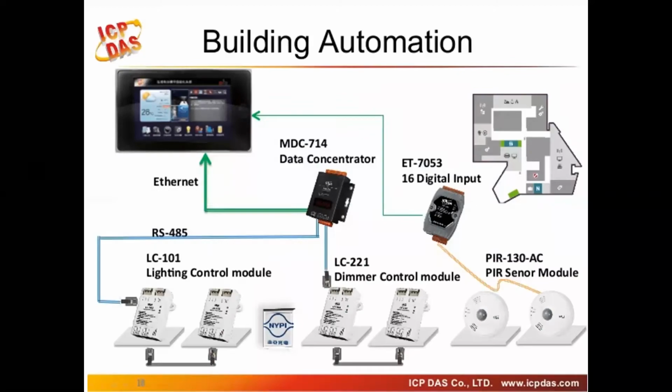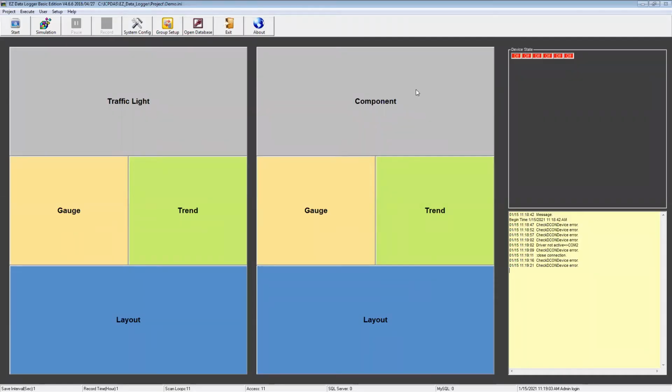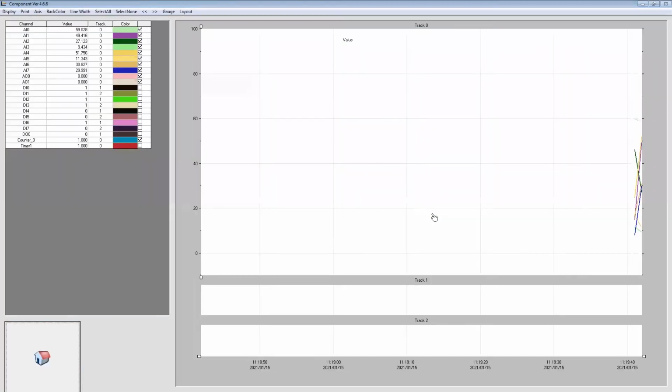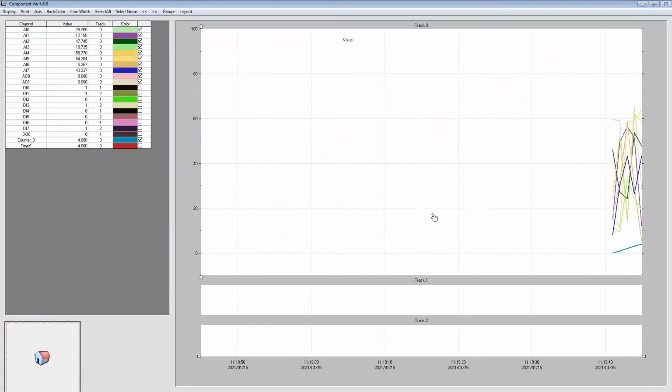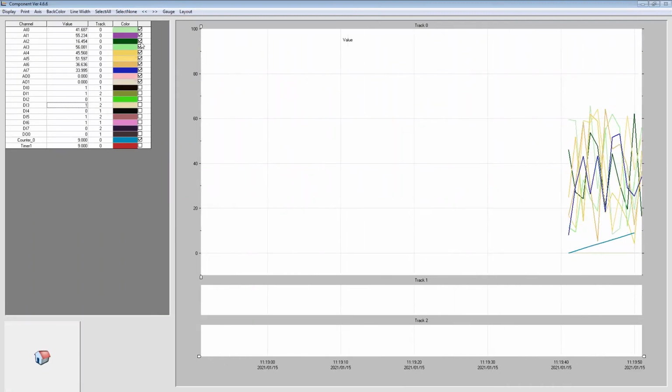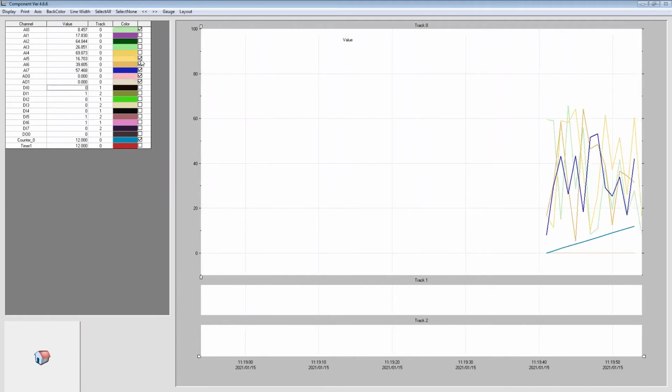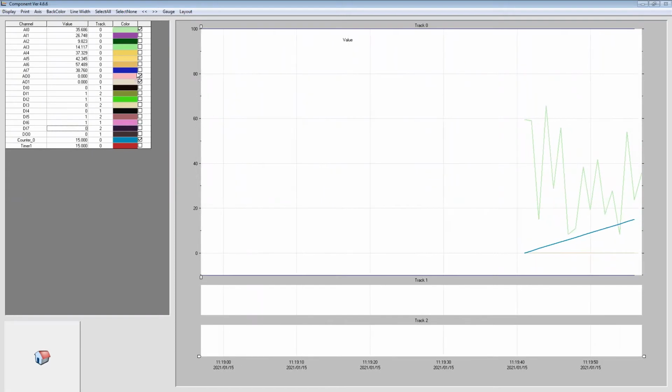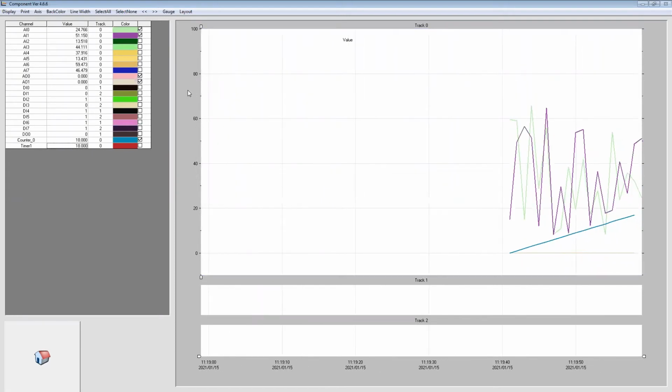Let me give you a snapshot of the software. Okay, this is our EZ Data Logger demo that comes with the software, just to show off the capabilities of the software. Let me enter simulation mode, and I'll show you some screens and what it looks like. The main screen that people use is the trend curve. This is to view the analog data and digital data in a nice snapshot to monitor a process like, say, level, temperature, or whatnot. You can isolate channels and select which channels to view, as well as have multiple workgroups to display different combinations of channels.